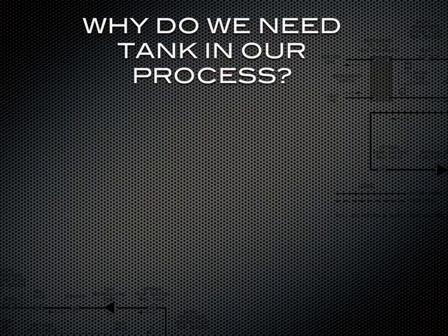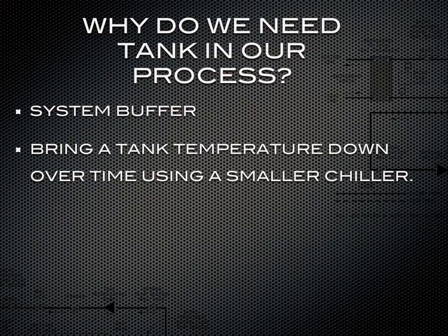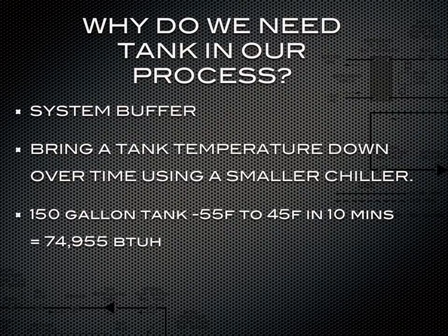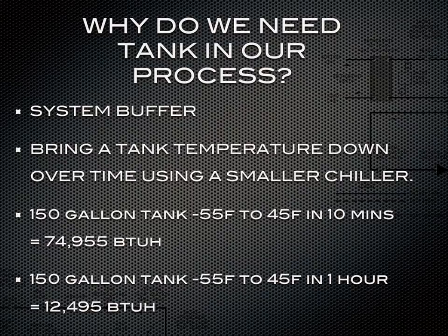Another good reason to have a tank in your process is it can act as a system buffer. A system buffer is bringing a tank temperature down over time using a smaller chiller. For example, if you have a 150-gallon tank and you want to bring it from 55F to 45F, you can do it in about 10 minutes with a 6-ton chiller. If you take that same tank from 55 down to 45, you can do it within about an hour with a 1-ton chiller. This is really good if you don't have a budget for a 6-ton chiller, but you do have a budget for a 1-ton chiller. And this is also good if you do not have a high demand of flow rate to your process. We have a lot of customers that do this.